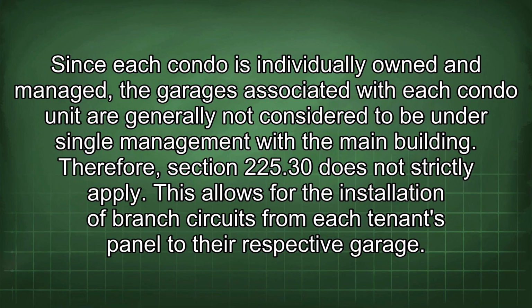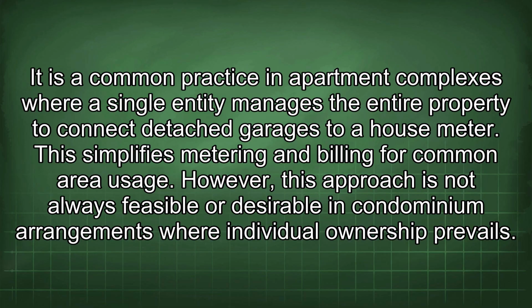Therefore, Section 225.30 does not strictly apply. This allows for the installation of branch circuits from each tenant's panel to their respective garage. It is a common practice in apartment complexes where a single entity manages the entire property to connect detached garages to a house meter. This simplifies metering and billing for common area usage.